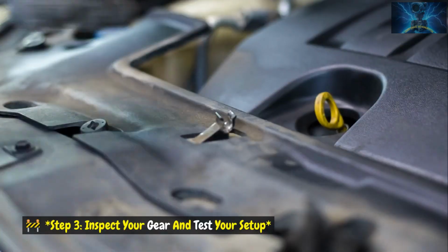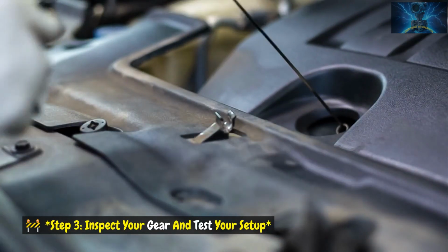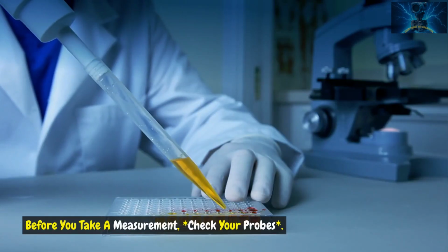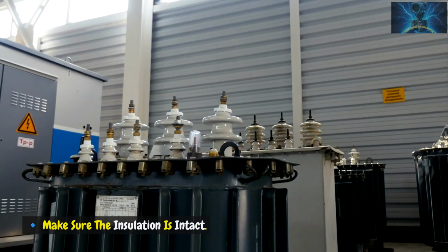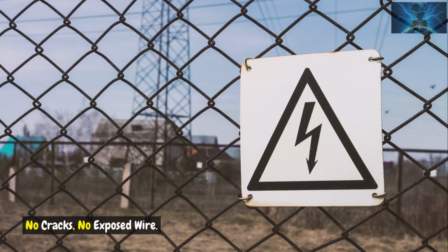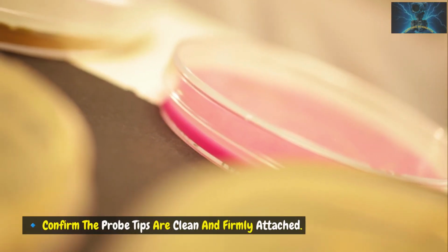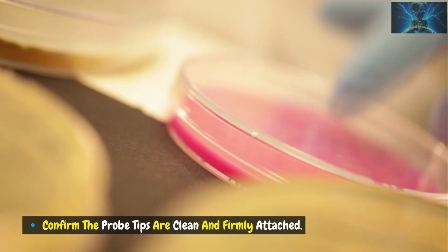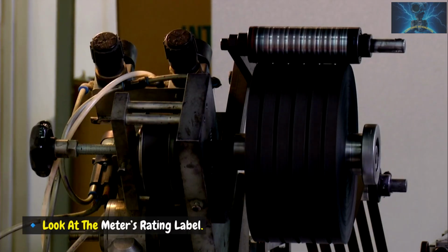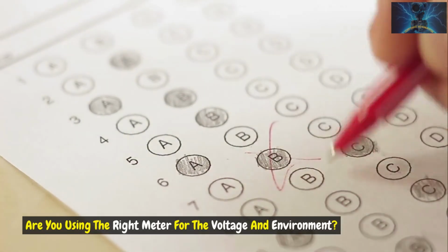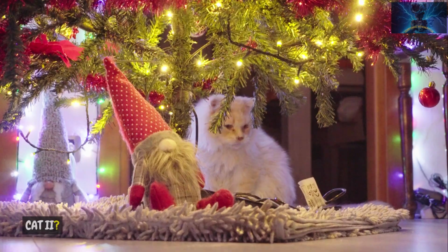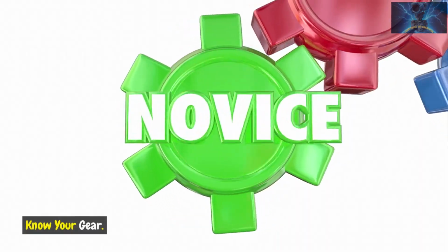Step 3. Inspect your gear and test your setup. Before you take a measurement, check your probes. Make sure the insulation is intact. No cracks, no exposed wire. Confirm the probe tips are clean and firmly attached. Look at the meter's rating label. Are you using the right meter for the voltage and environment? Cat 2? Cat 3? Know your gear.